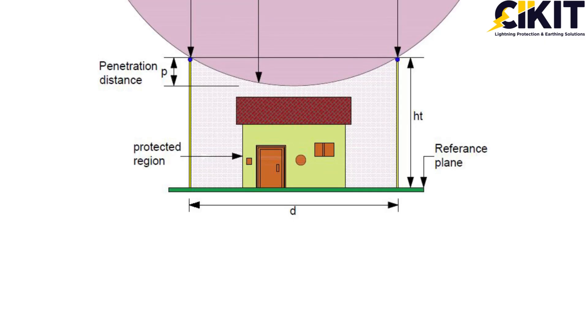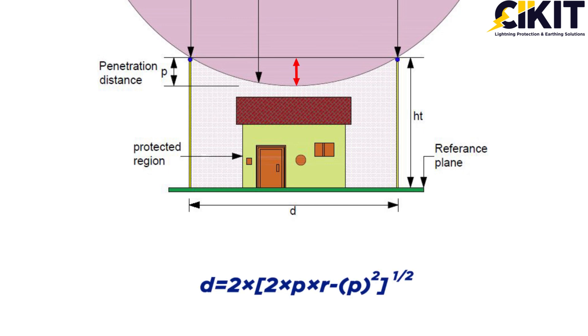IS/IEC 62305 Part 3 has provided the formula for calculating the maximum permissible distance between two air terminals so that the sphere won't make contact with the structure to be protected.